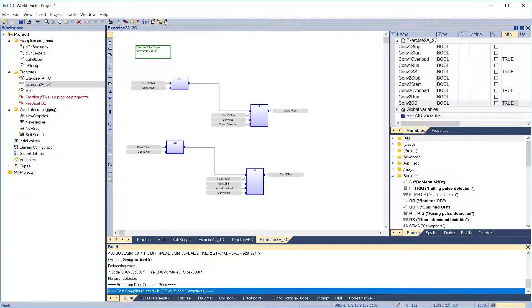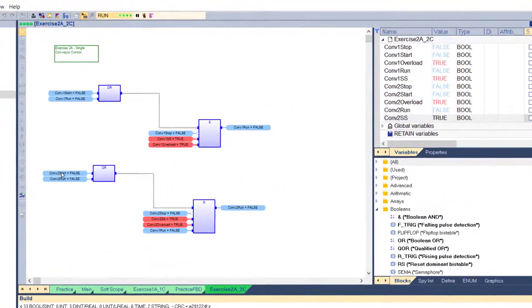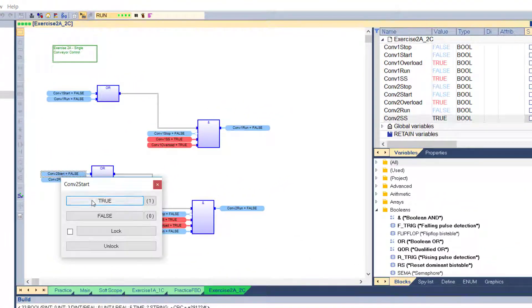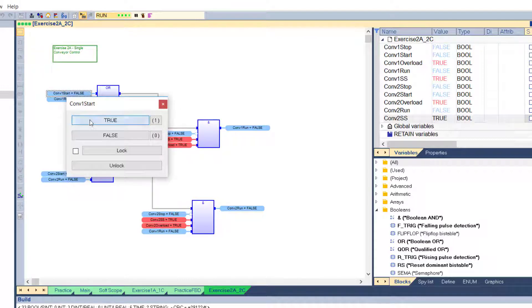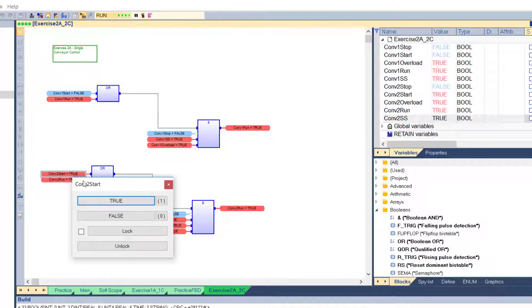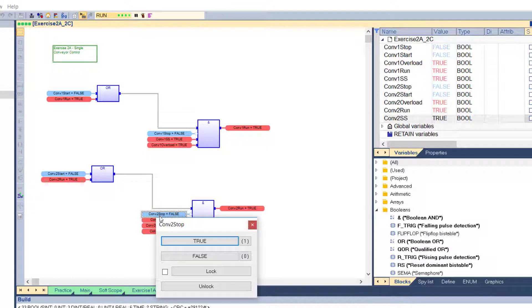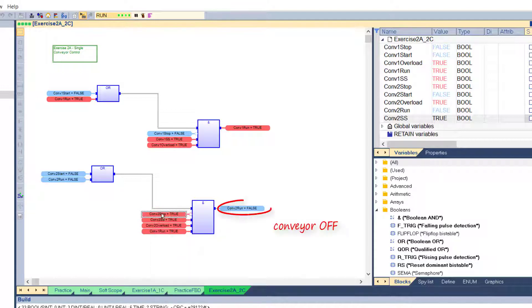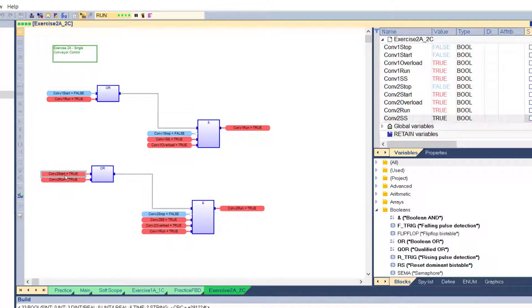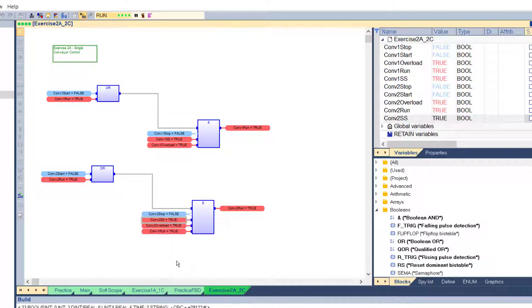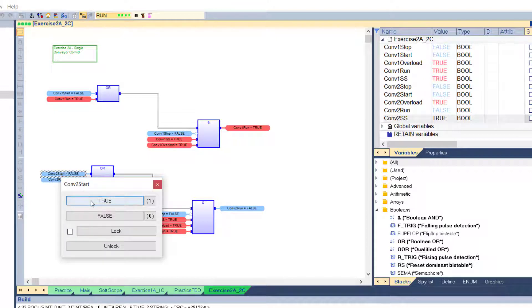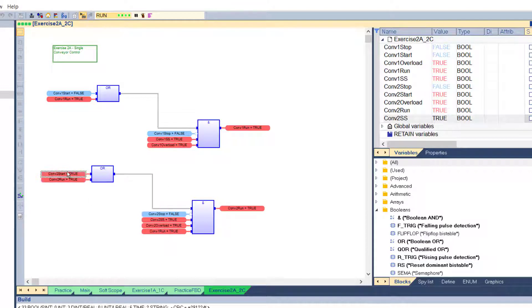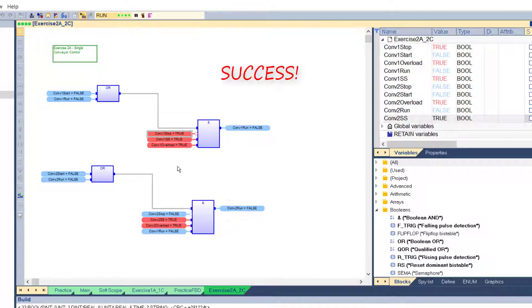Compile and run in the simulator. Turn on conveyor 2 start. The conveyor doesn't start because conveyor 1 isn't running. So start conveyor 1, and now start conveyor 2. It comes on. Check the stop and safety stop switches. And finally, verify that if we turn off conveyor 1, conveyor 2 also goes off. And it does. Another successful application.